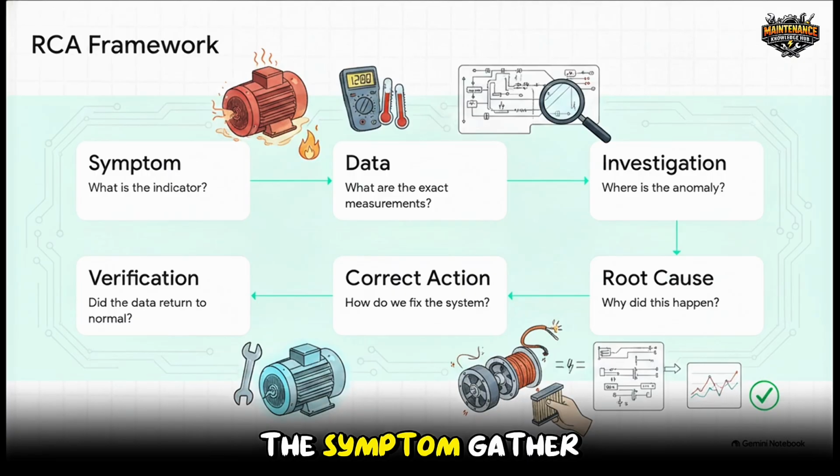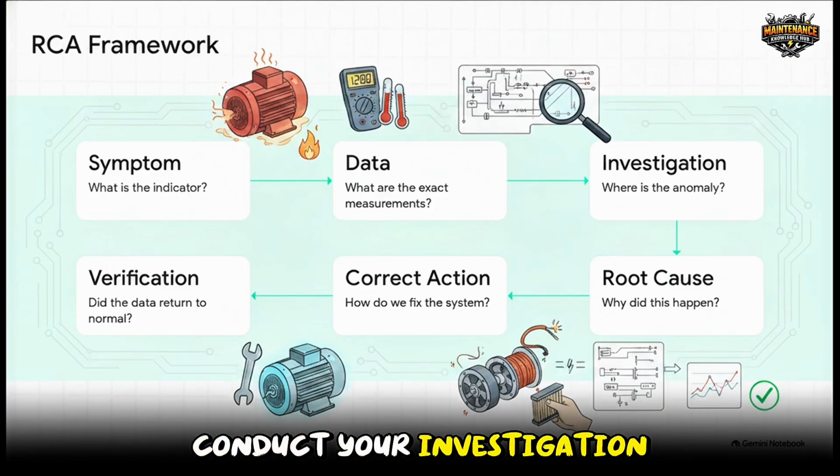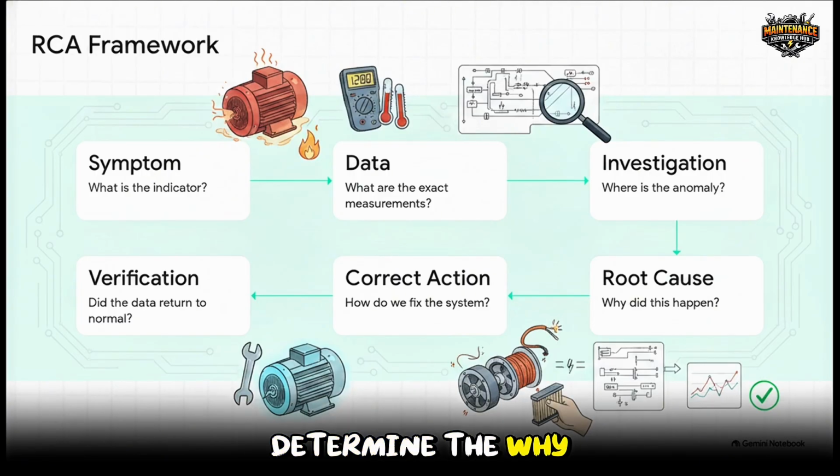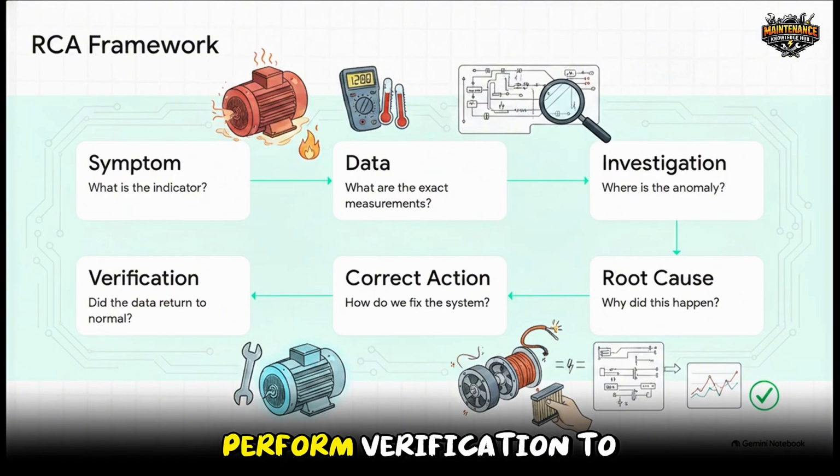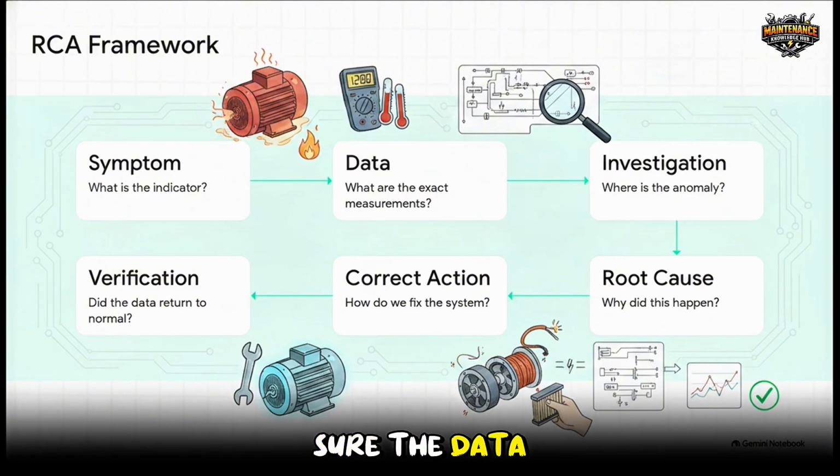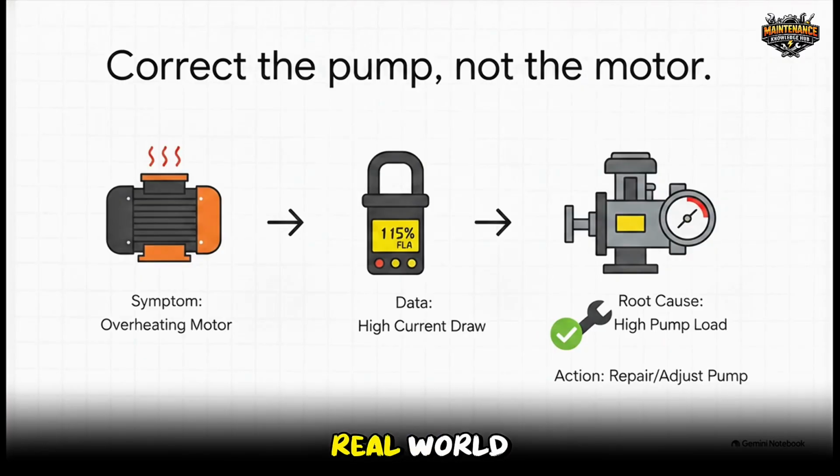You start with the symptom, gather the hard data, conduct your investigation to find the anomaly, determine the why or the root cause, execute a corrective action, and this is the big one, perform verification to make absolutely sure the data return to normal. We do this instead of just lazily swapping out a burnt motor for a new one. Because guess what? That new motor is going to suffer the exact same fate if the real problem is still hiding in the system. Let's look at how this plays out in the real world.